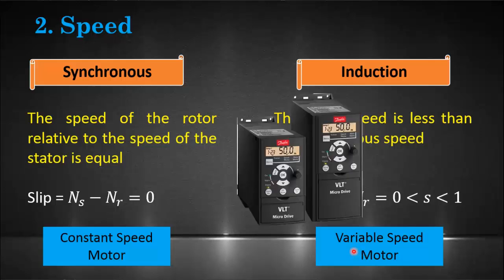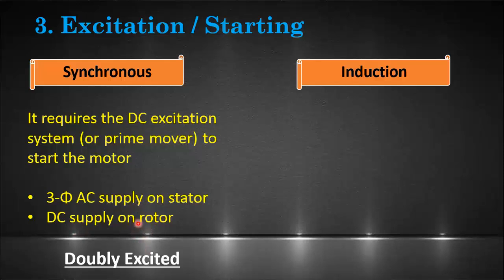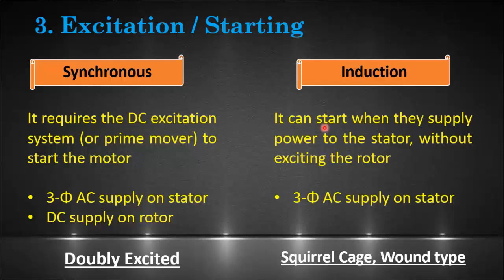The third difference is based on the excitation or starting method. The synchronous motor requires a DC excitation system or a prime mover to start. Two different supplies are needed: a three-phase AC supply on the stator and a DC supply on the rotor, which is why it is called a doubly excited motor. The induction motor can easily start with only a three-phase AC supply on the stator, without exciting the rotor. There are two types of rotor: squirrel cage and wound type.